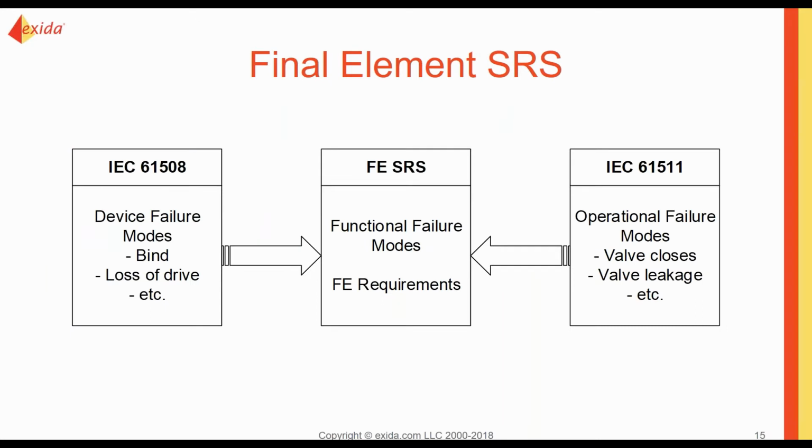What I would propose is that final elements really are bespoke systems. They're going to be unique for each installation. They're going to need additional rigor than just the 511 SRS, and if we treat them as such, we can define a process around them that's going to let us record our requirements and then test and validate we've met them.